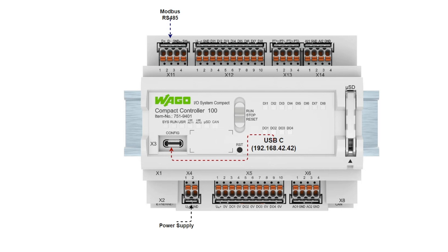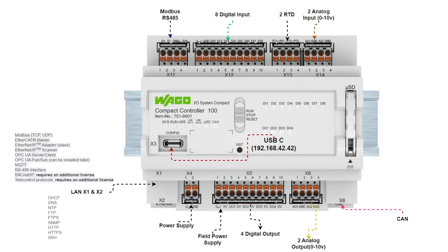It has Modbus RS-485 and 8 digital inputs. Then two RTDs we can configure — this variant doesn't support PT100 but we can configure it as a raw input. There are two analog inputs supporting 0–10V, two analog outputs also 0–10V, and 4 digital outputs with field power supply. CAN protocol is supported at a different port, and we also have Modbus, EtherCAT, Ethernet IP, OPC UA, MQTT, BACnet, telecontrol protocols, and different internet protocols including FTP.